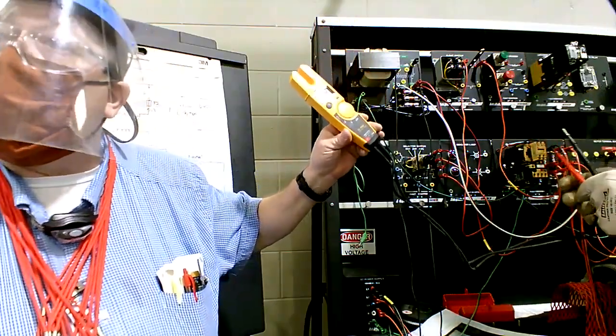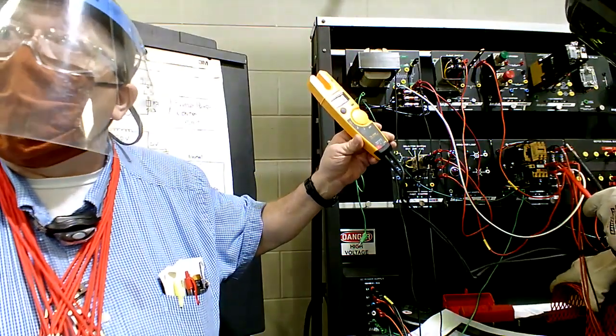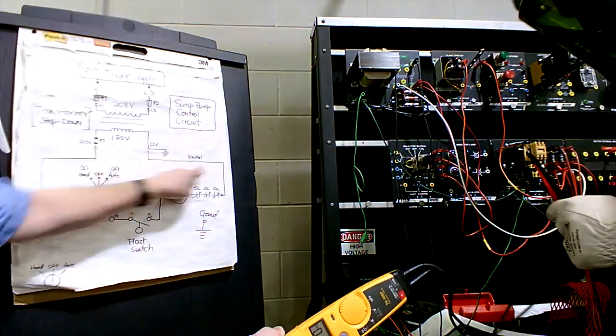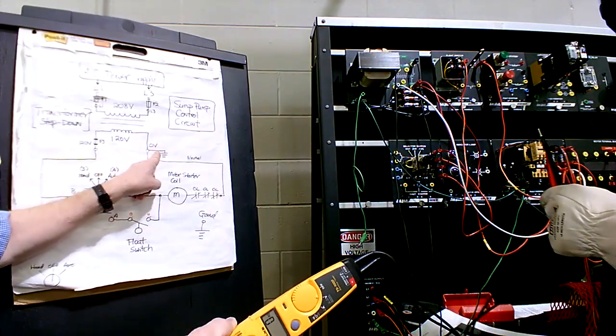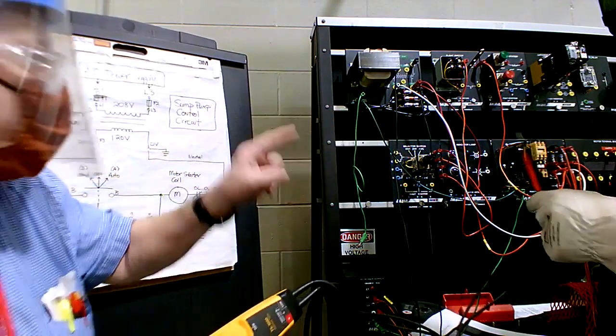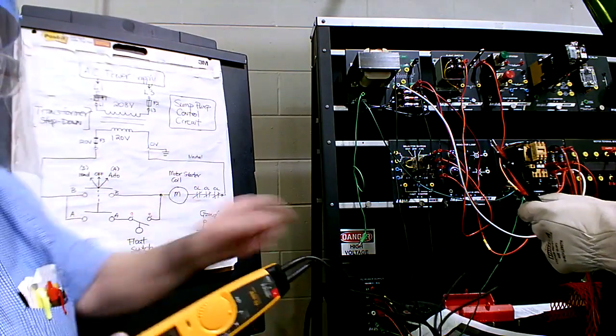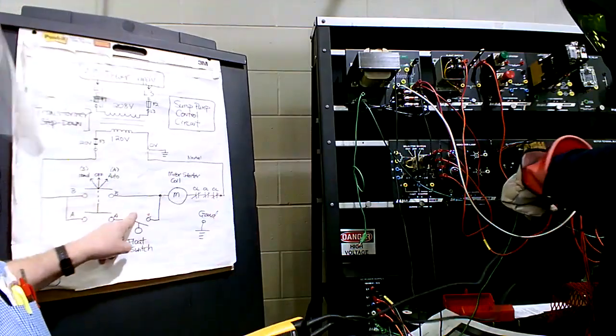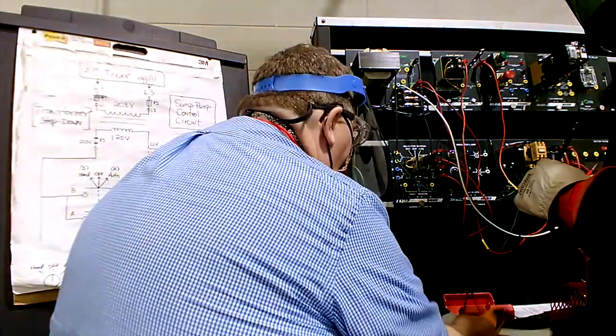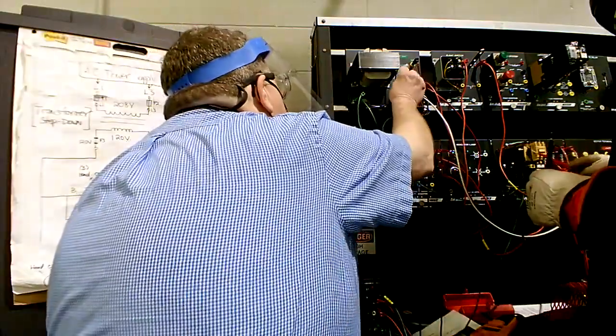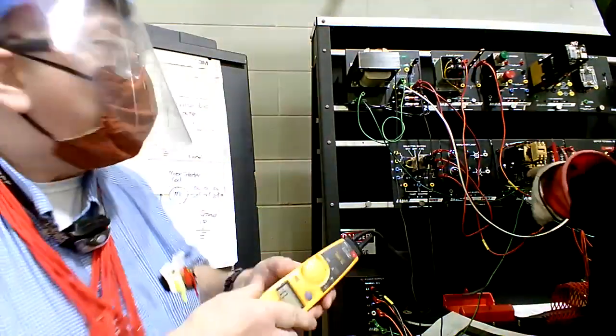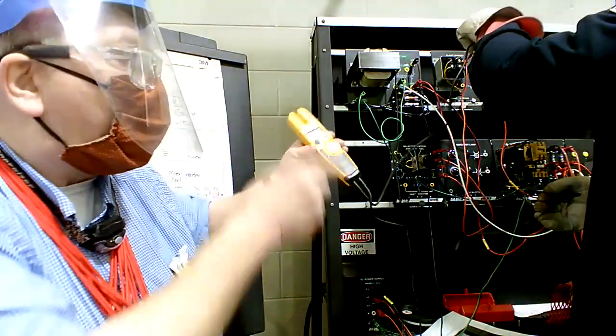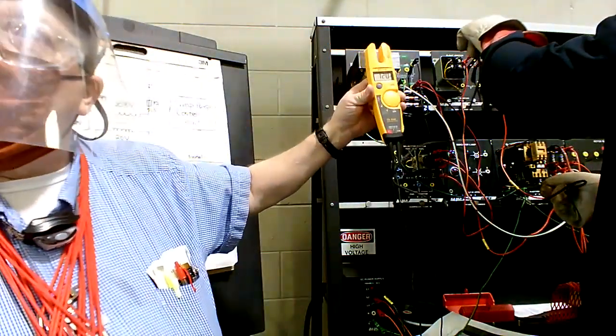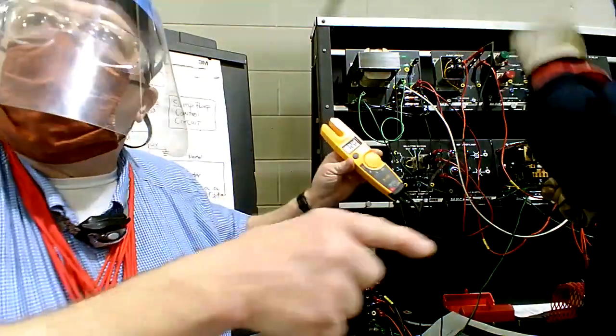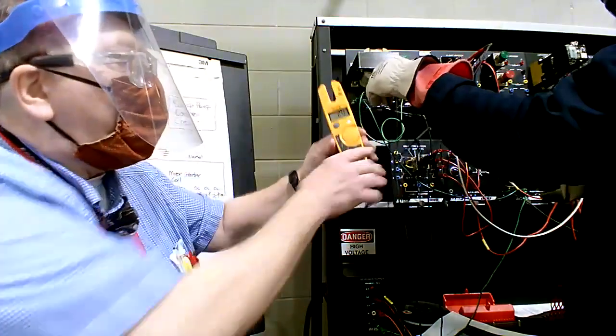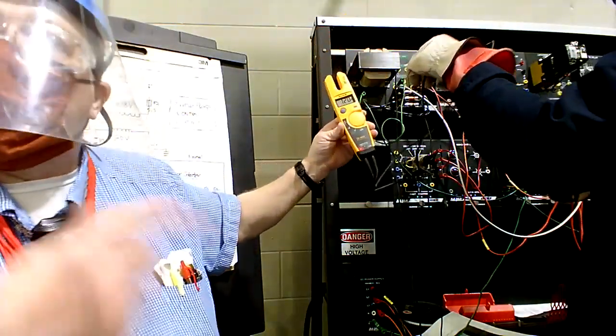What we're looking at here in the book talks about floating and grounded secondaries or controls. The idea is you've been grounding your neutral wire on all of your circuits. If you do ground them, you can take your meter and go from any grounded point in that circuit with one probe, and then take your other probe and do your test points. Now demonstrate it again. Watch close. We've got neutral grounded right now. He's going from a different ground point to the float, and he's getting 120. So you can use any grounded point for a reference if you have your neutral grounded. No matter where you go, it's 120 in that circuit, from any ground to the float.